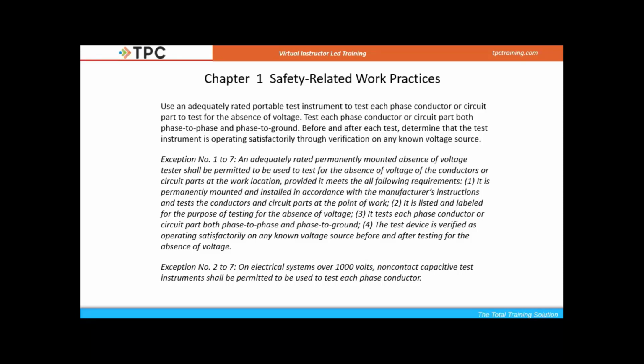And unfortunately, one of those transients burnt out an electrical component in his meter, and his meter was broken. So his meter was not giving him an accurate reading. If he would have gone back and tested that receptacle again, he would have known that his meter was broken, but he didn't do it. He took an Allen wrench out, which was an uninsulated Allen wrench, put bare hands on it, put it right into a lug, and the man was electrocuted that day. He lost his life. So this is an extremely important step right here.